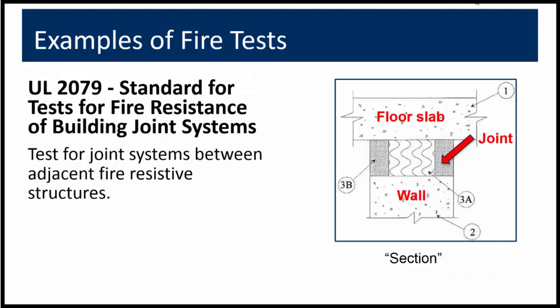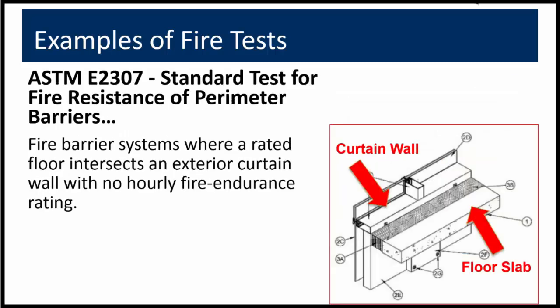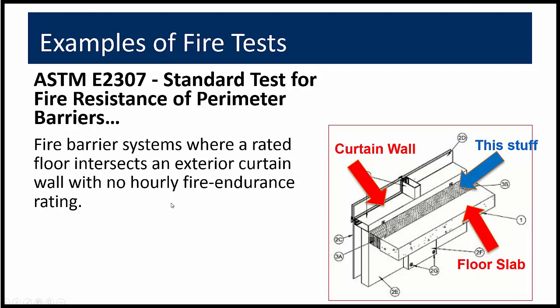UL2079 is applicable to joint systems that are intended for use in linear openings between adjacent fire-resistive structures. For example, the illustration shows the joint where a fire rated wall meets a fire rated floor slab. The joint materials we are most familiar with include the various fire caulks. ASTM E2307 applies to perimeter fire containment systems where a rated floor adjoins a curtain wall with no hourly rating, and addresses the materials intended to fill the gaps between the floor and curtain wall to prevent the vertical spread of fire in the building.